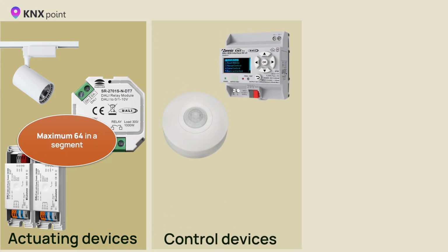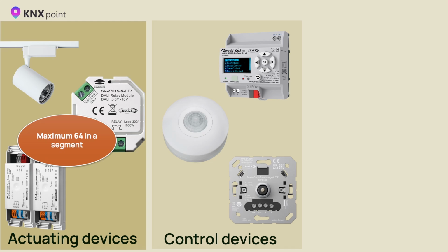Control devices and controllers that send commands to the DALI bus. Their number is generally limited only by the total current drawn from the bus. However, in the DALI 2 standard, some of these devices may have their own addresses, so there can be no more than 64 addressed devices.